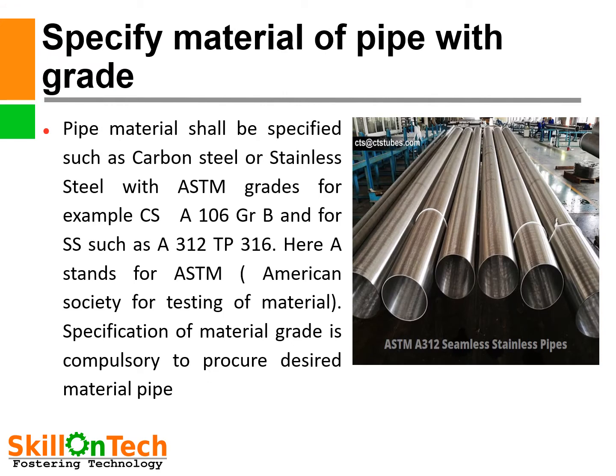Specify material of pipe with grade. Pipe material is very important; therefore, while procuring a pipe, we must specify the material. Pipe material shall be specified with ASTM grades — for example, carbon steel A106 Grade B, and for stainless steel, A312 TP316. There are various grades available in the market, so we should specify the correct grade. Here, 'A' stands for ASTM — American Society for Testing of Materials. Specification of material grade is compulsory to procure the desired pipe. A SS pipe showing ASTM A312 seamless stainless steel pipe is shown in the picture.